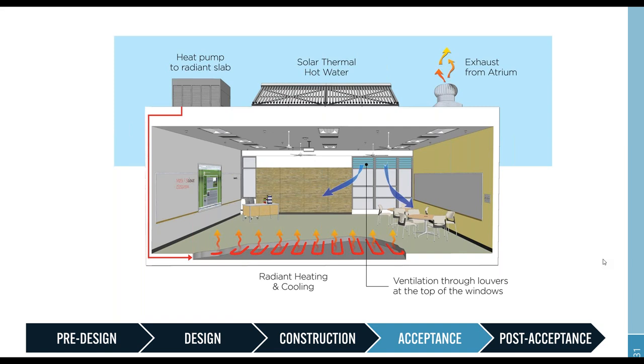What we discovered coming in rather quickly, as we started our investigation on the radiant floor side of things, was a slew of sensors that were miscalibrated, both in the slab and temperature sensors that just weren't set up correctly, along with controls logic that wasn't making sense for the equipment that was installed. A radiant system is inherently slow to react, as you need to heat up an entire floor slab or cool it down in order to meet the conditioning. But the controls were set up to be quick reacting, similar to a VAV system. So what this resulted in was condensation on the floor in some cases, where the janitors would have to come in and mop up wet spots on the floors, and would also result in just uncomfortable spaces.